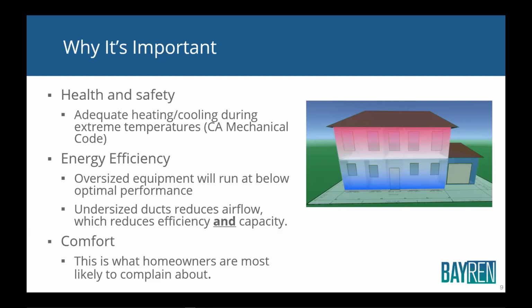Undersized ducts, as opposed to the equipment, reduces airflow, which reduces efficiency and capacity. And what has happened in most of the country is over the years, the fear of undersizing equipment has driven up the size of the equipment, and the desire to keep the cost down has reduced the size of ducts, because one of the biggest costs of installing a duct system is labor. And small ducts are easier and faster and cheaper to install. So over the years, equipment has gotten bigger and ducts have gotten smaller. And that's a really bad combination, okay?